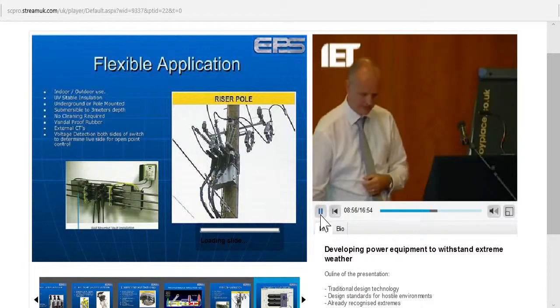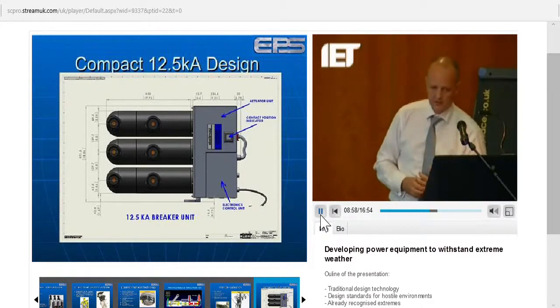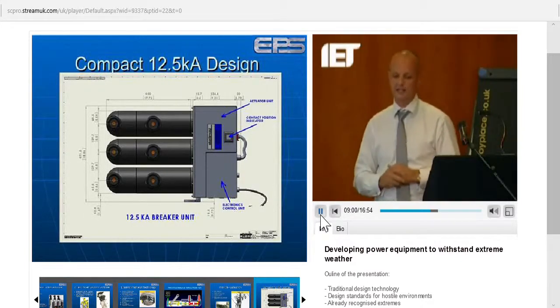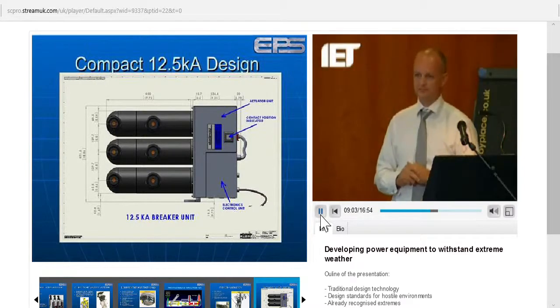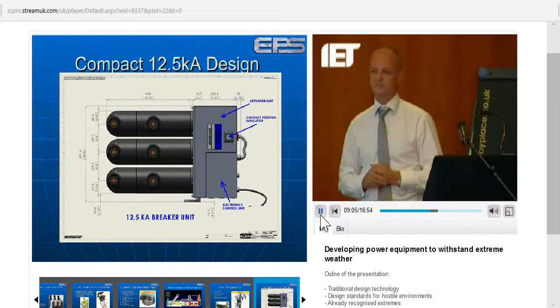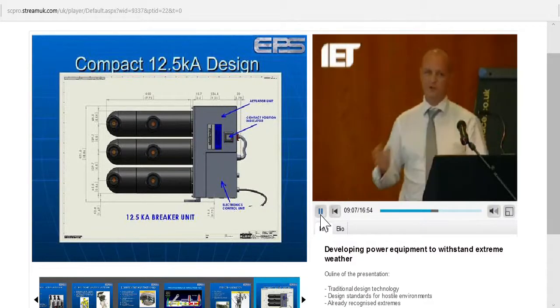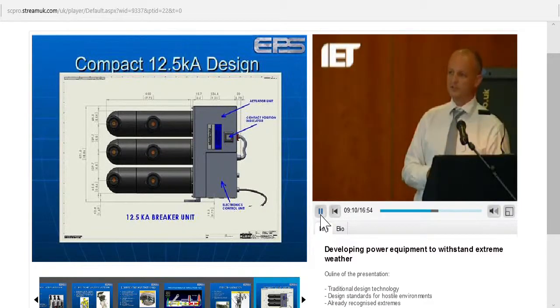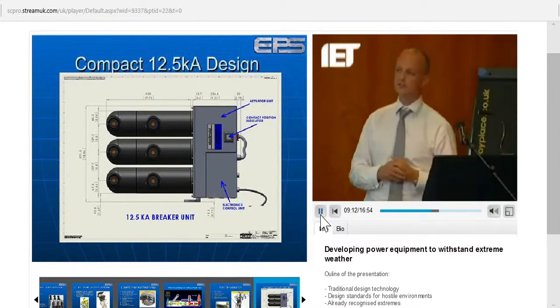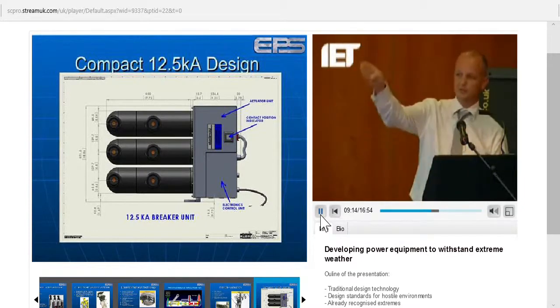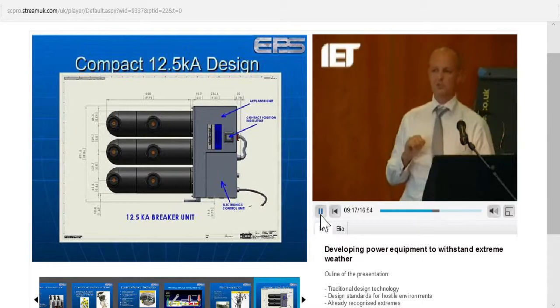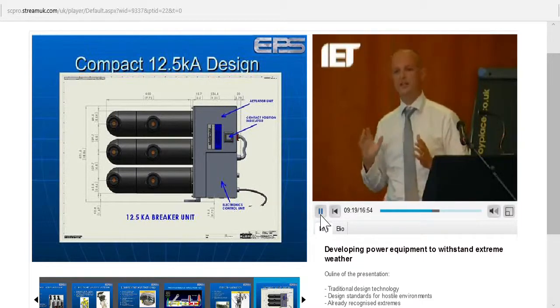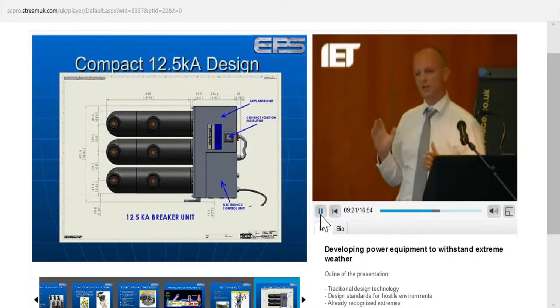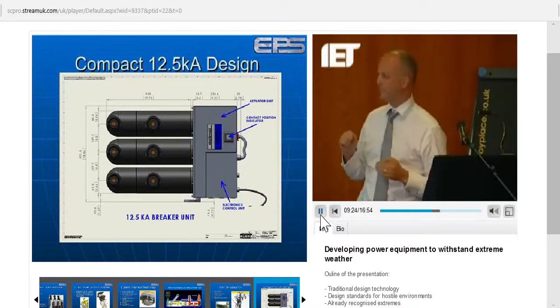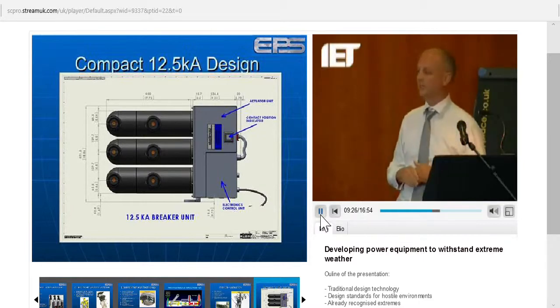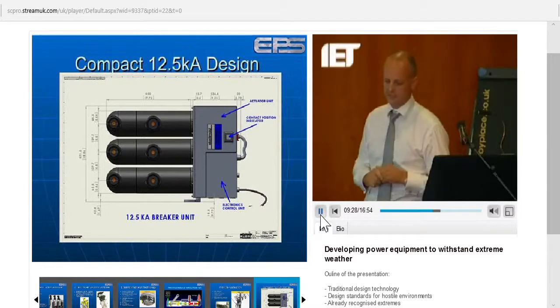It's very compact. The model that I sent round to you there is in fact quarter scale, and this is a 38 kV circuit breaker. For those of you not familiar with circuit breakers, a 38 kV traditional design circuit breaker would be about the size of that speaker pole there. Because we're able to condense that high stress voltage across a solid dielectric, we're able to compact to approximately 1/3 the size of a traditional circuit breaker.